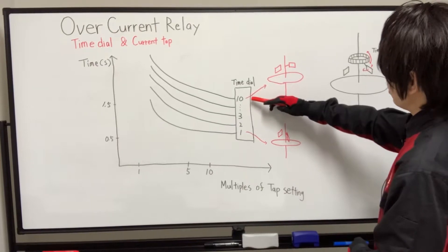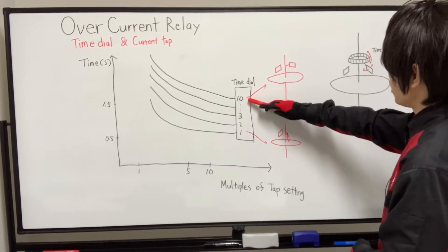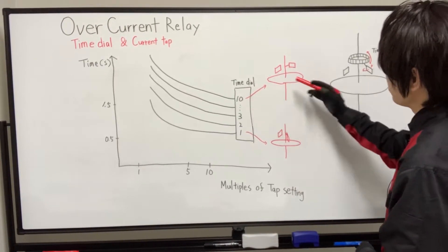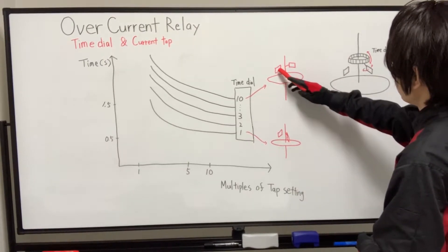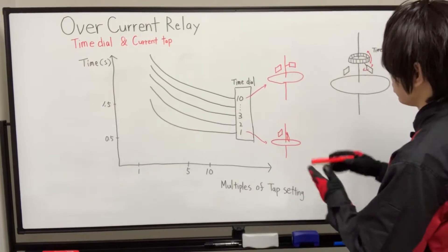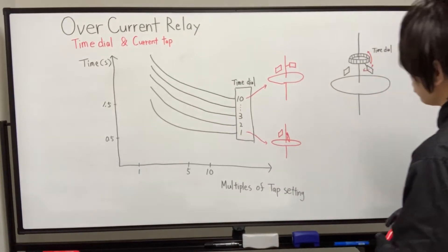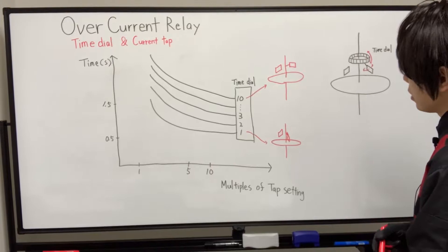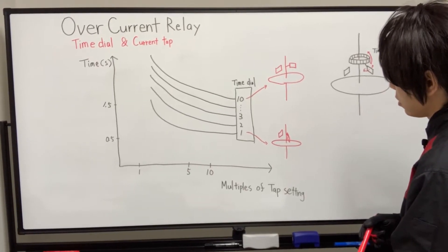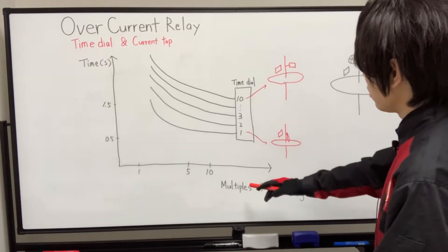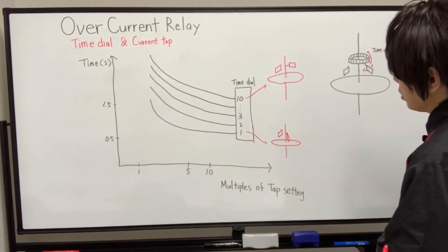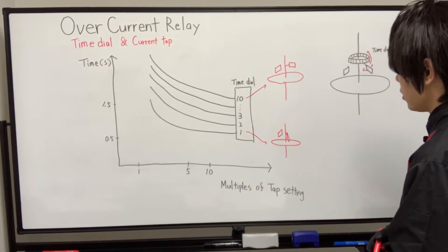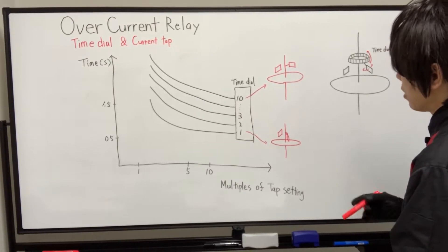While if the time dial is set to number 10, that gives us the longest operating time, so the distance is relatively long. When reading these curves, please remember the value of the current along the base is expressed relative to pickup current, that is, as a multiple of tap setting.